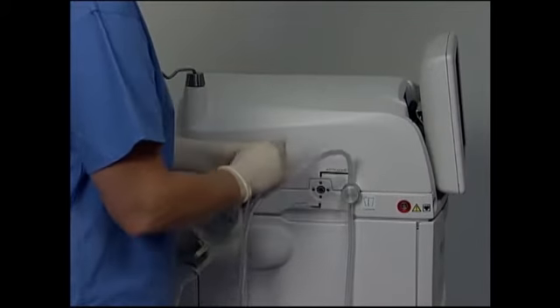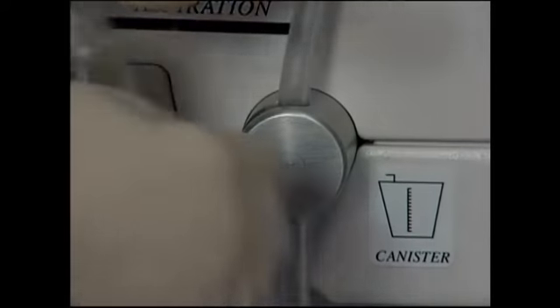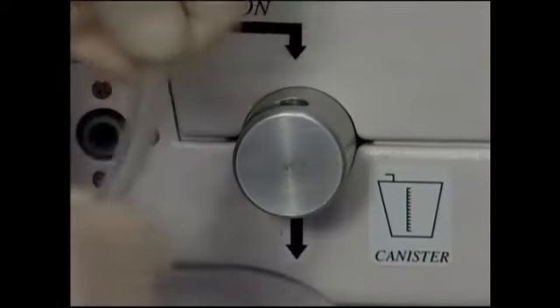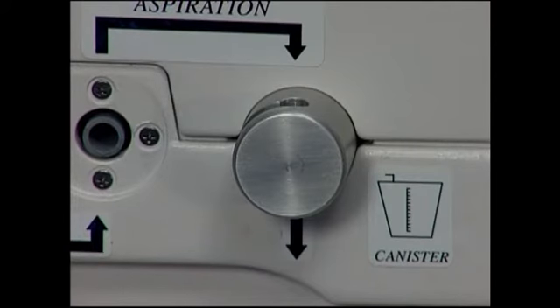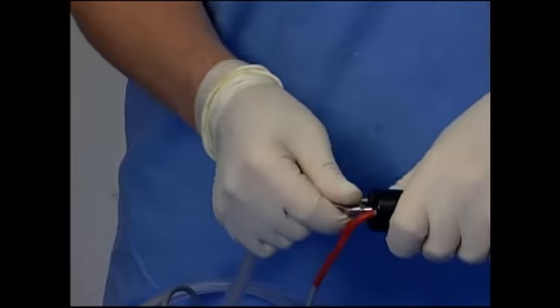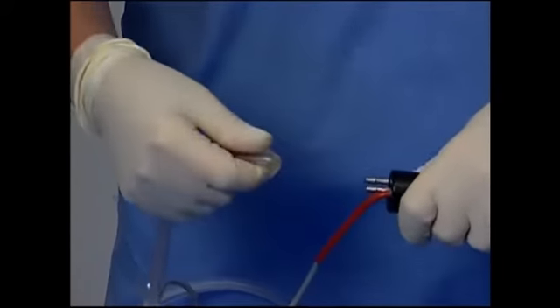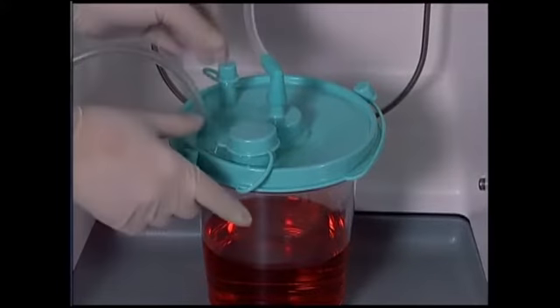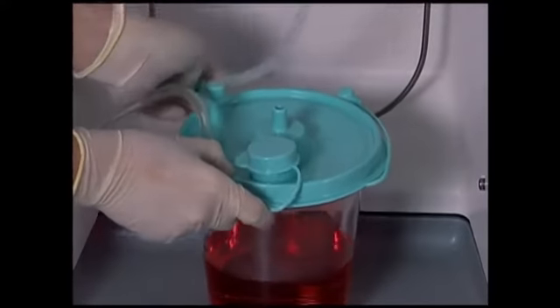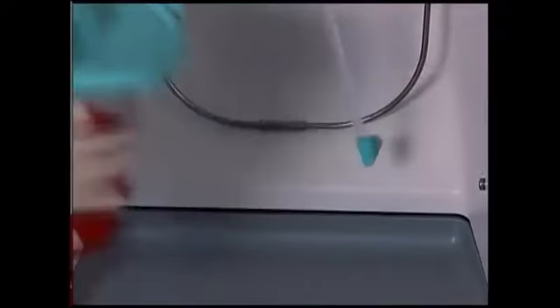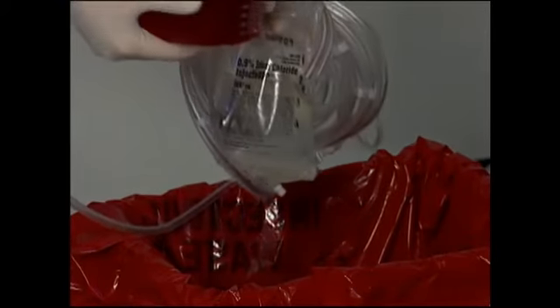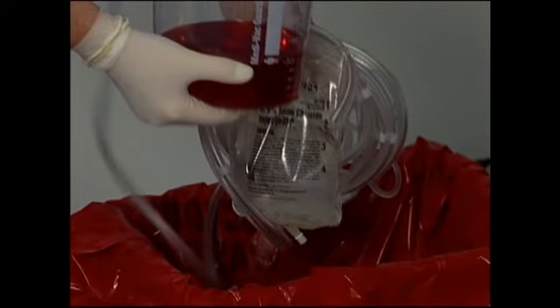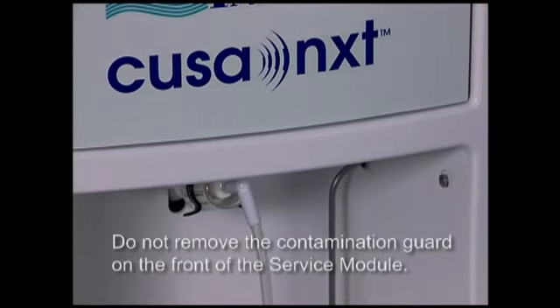Pull the aspiration filter out of the connection port and remove the aspiration tubing from the pinch valve on the side of the console. Disconnect the tubing set from the handpiece. Disconnect the contamination guard tubing from the vacuum port on the waste collection canister, then discard the canister, IV bag, and the tubing set together. Do not remove the contamination guard on the front of the service module.